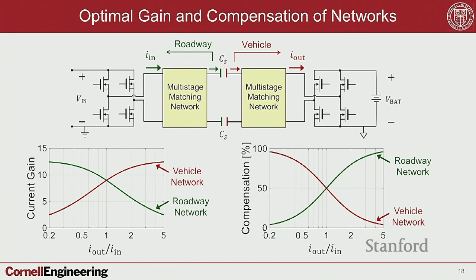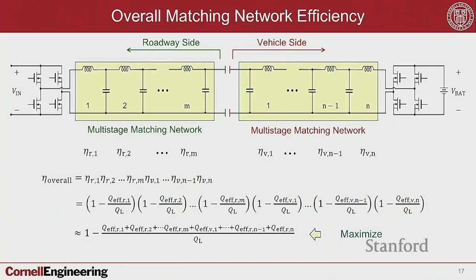The conventional thinking was that if you have a large reactance, you want to compensate it from the very first stage closest to it on either side. That makes sense conventionally, because that's where your currents are smallest. So if you're putting in a large inductor, it's carrying the smallest current, so it's best to do it up front. We discovered that this is actually not exactly true.